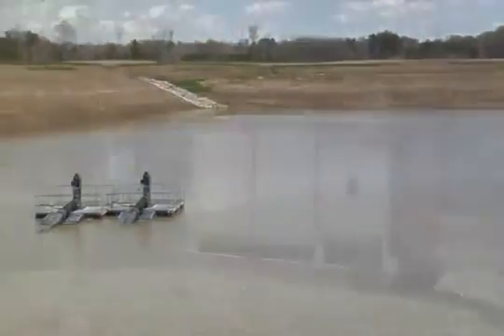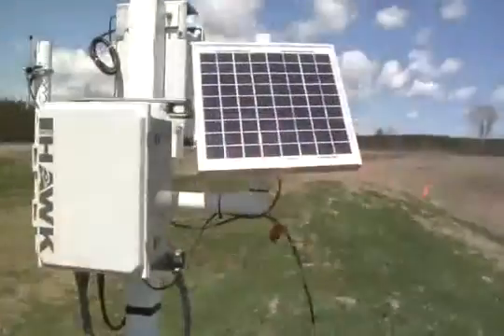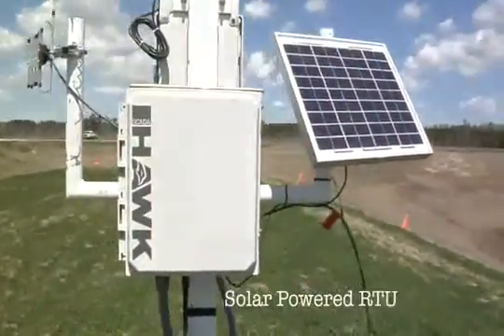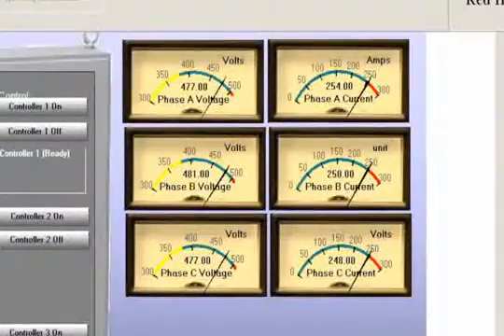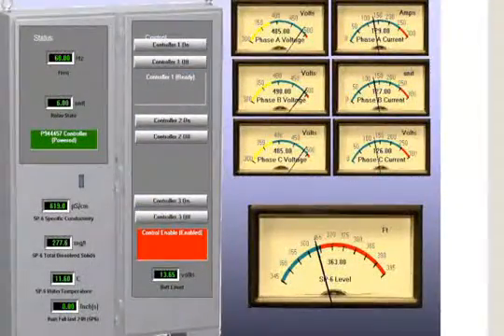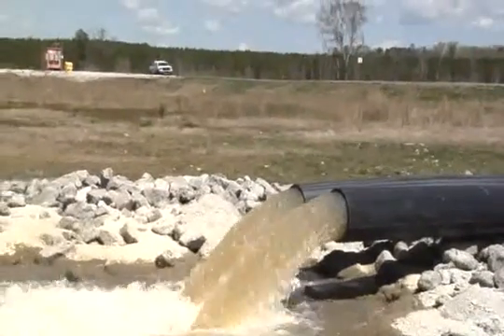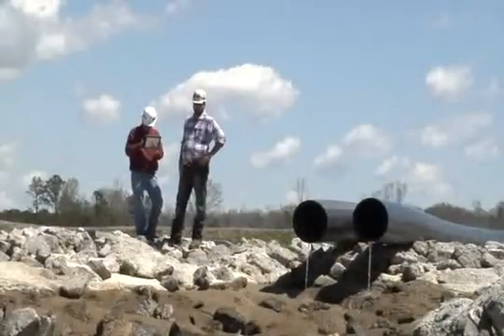At the sediment pond, two RTUs are installed. The main RTU is located near the switchgear and a solar powered RTU is located near the pond. The main RTU is collecting rainfall information, incoming power quality, pump current draw, and pump fault. It also enables remote starts and stops of the pump, as well as the automatic shutoff of the pump at a predetermined user-defined elevation, which is determined by a pressure transducer.